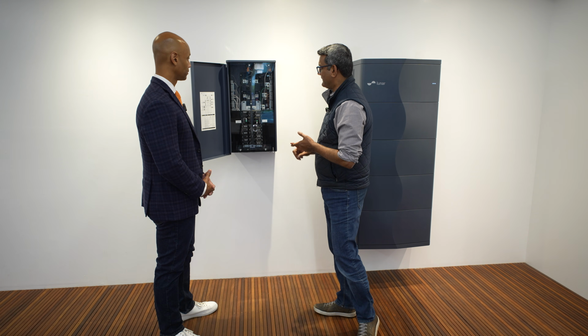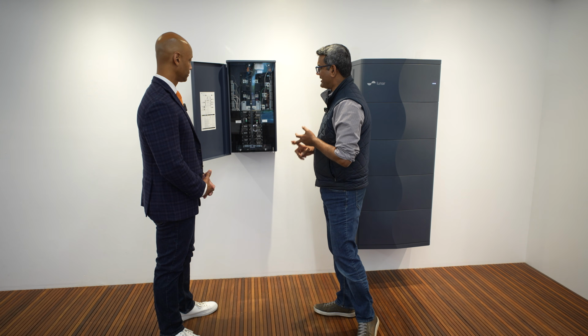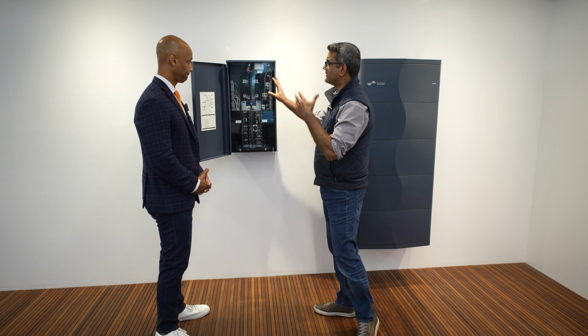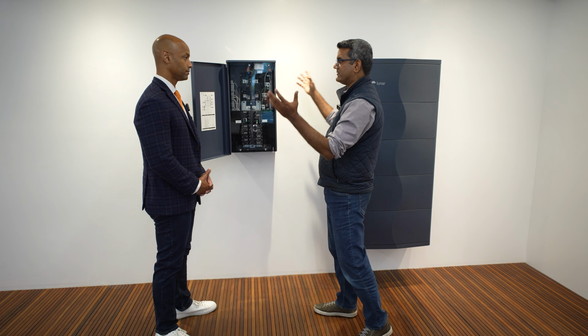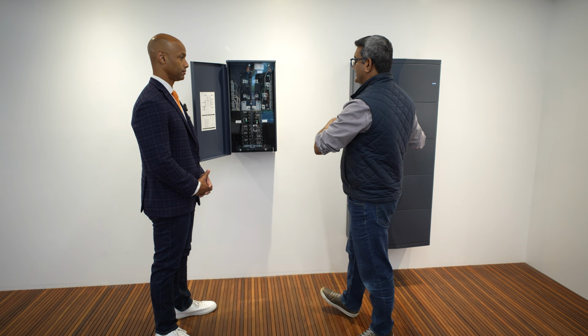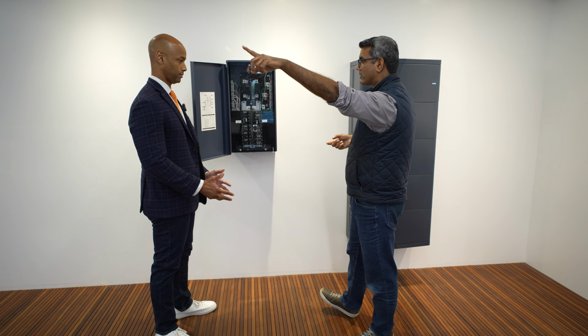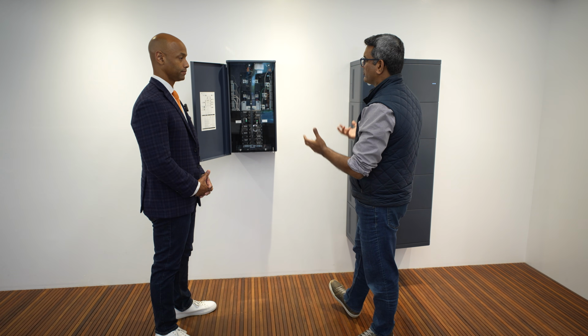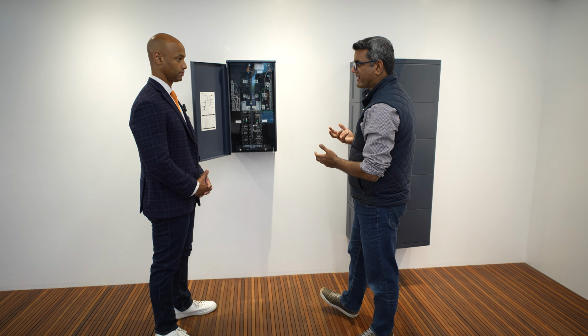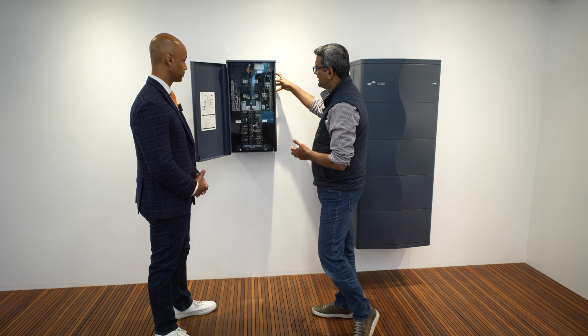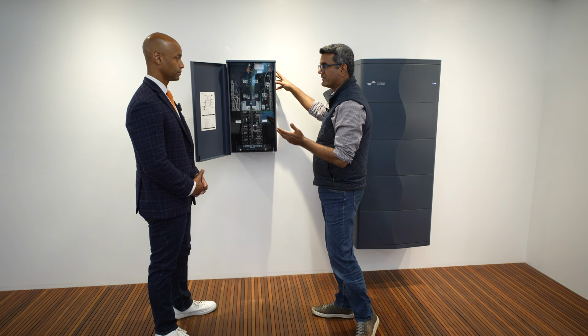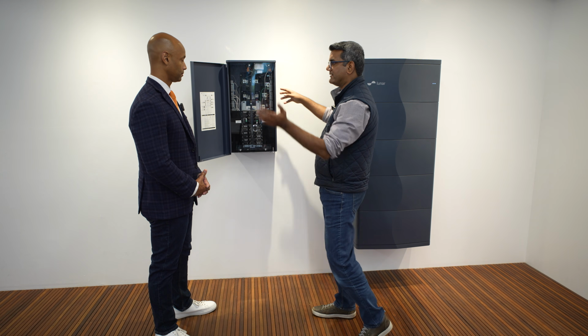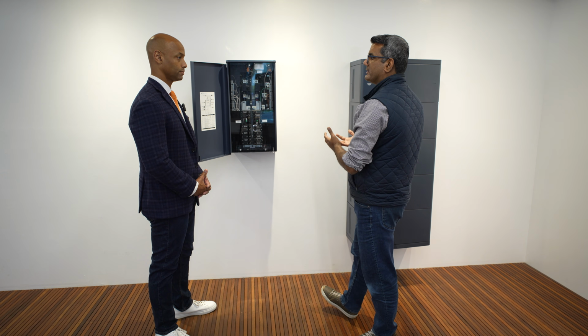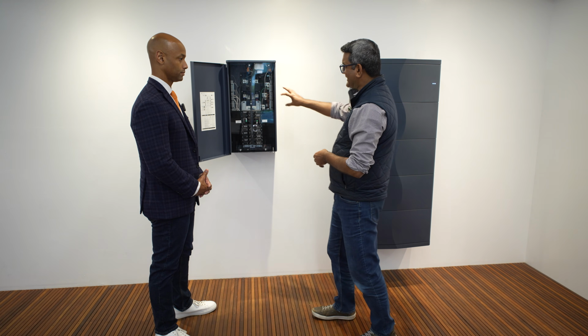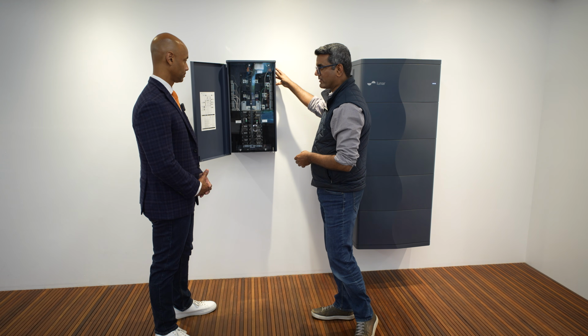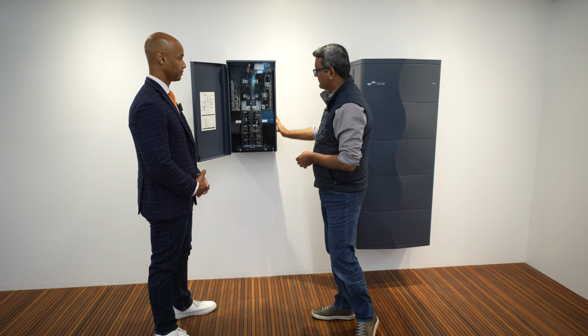The second plus is, when the utility power goes out, you can't just feed solar and battery power into the grid because there could be a line worker working. So you need some sort of relay or transfer switch mechanism. We have a built-in relay which opens up the moment the grid loses power, and then solar and the battery become the microgrid of the home. That capability is inside this lunar bridge.